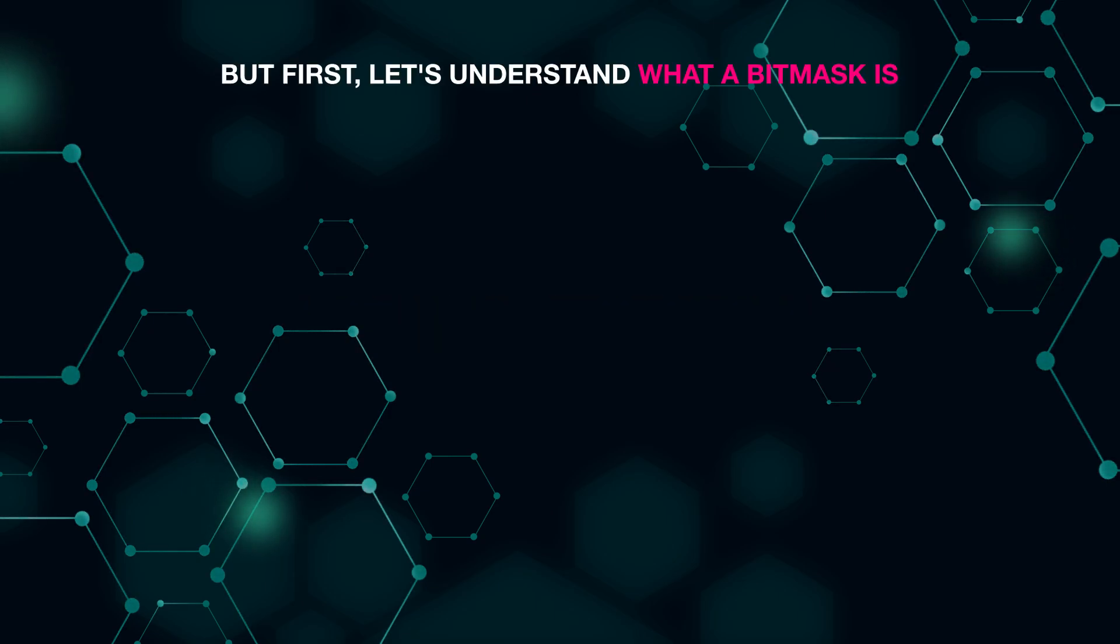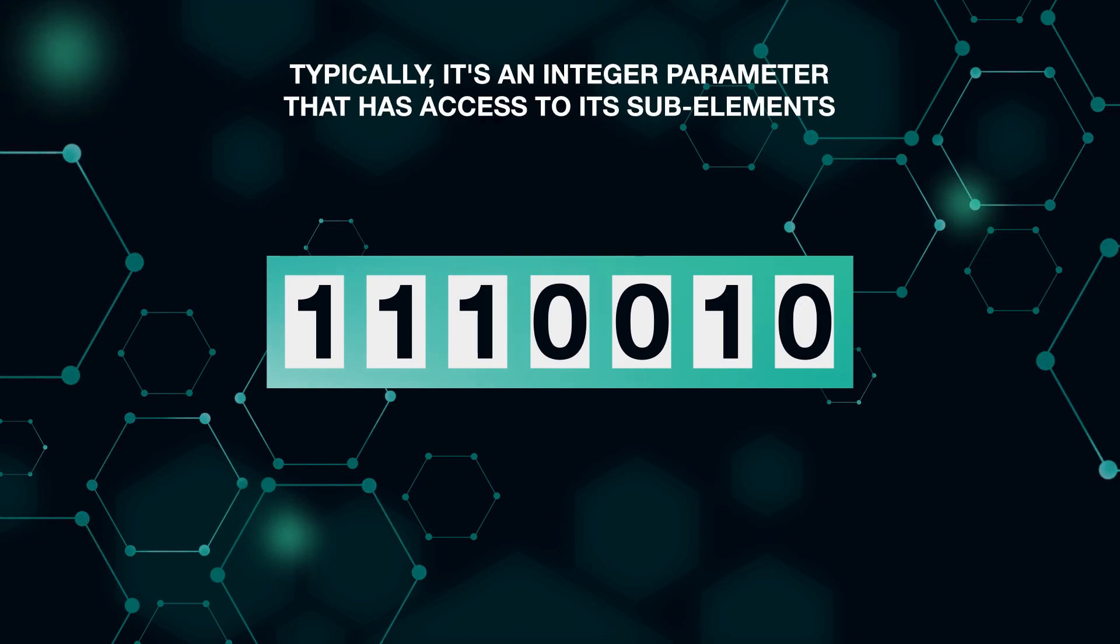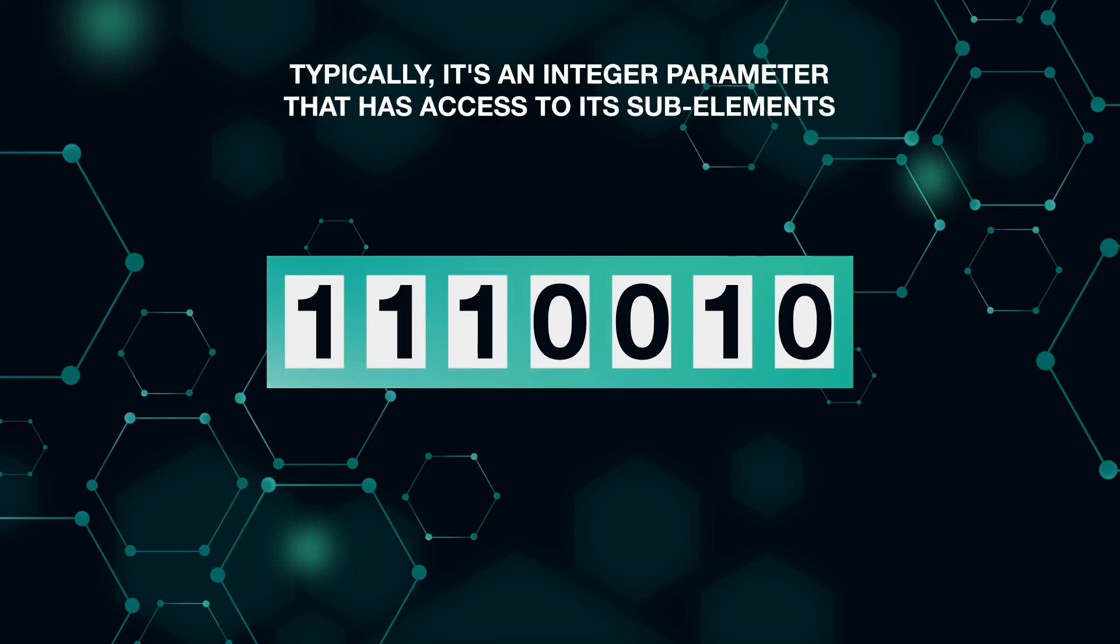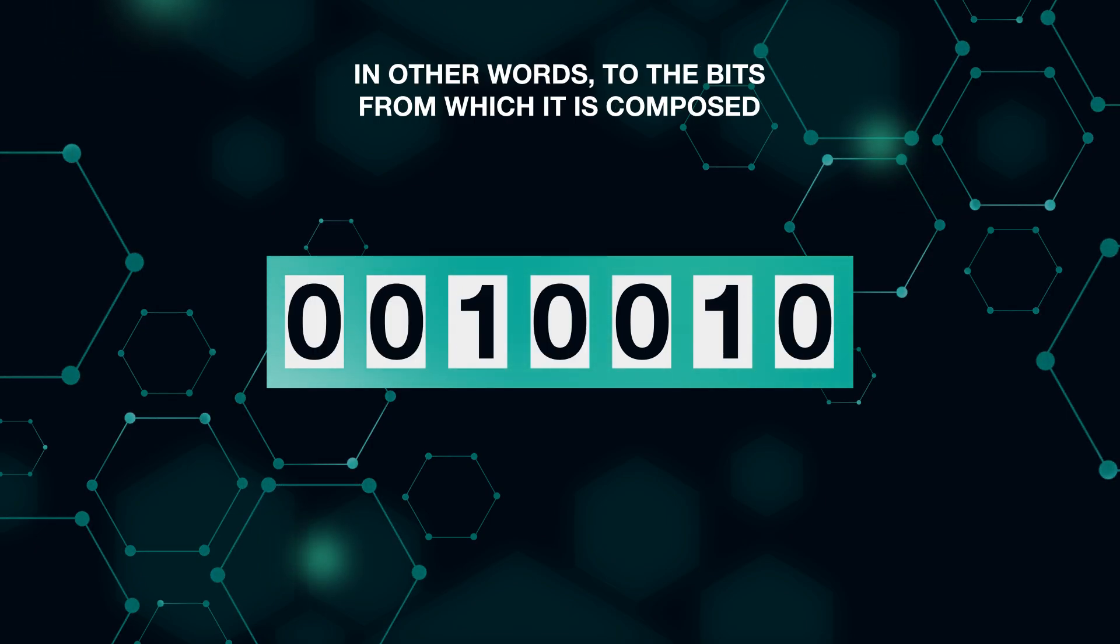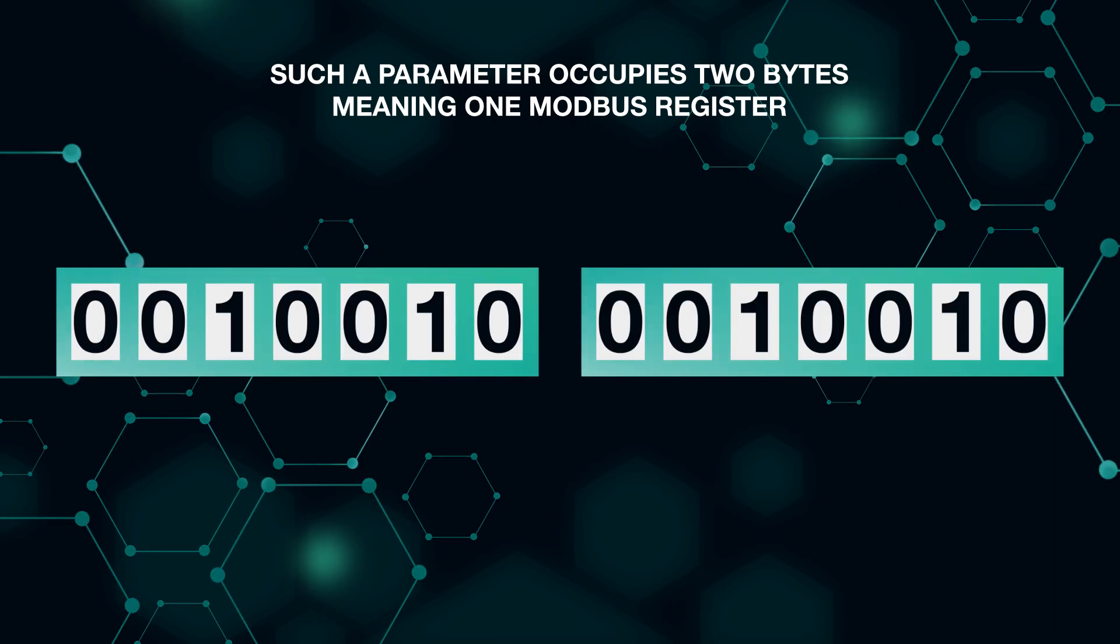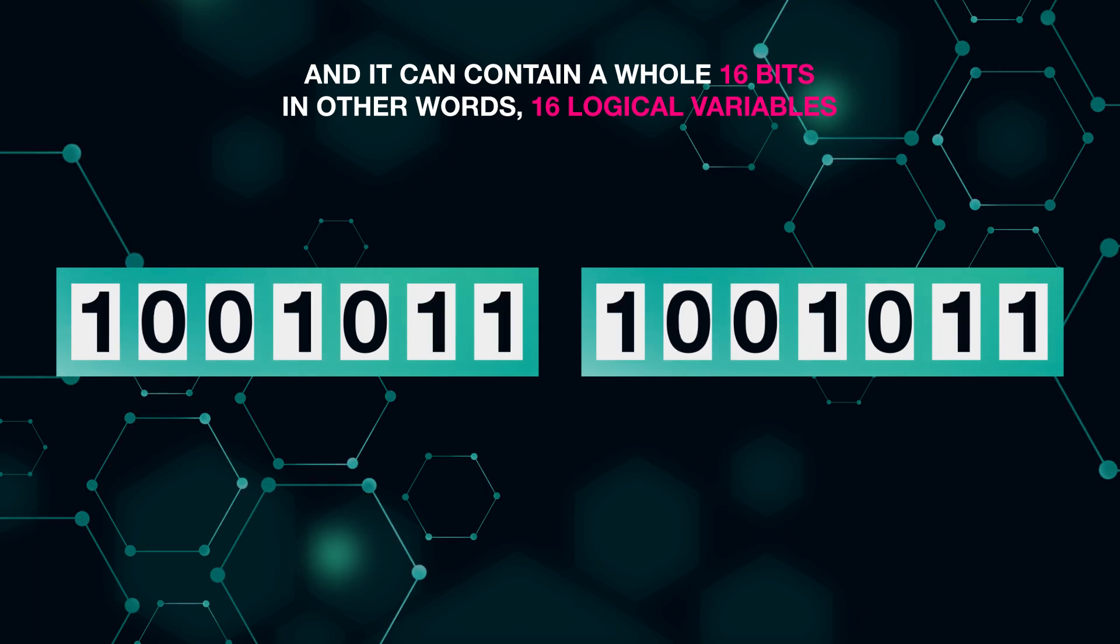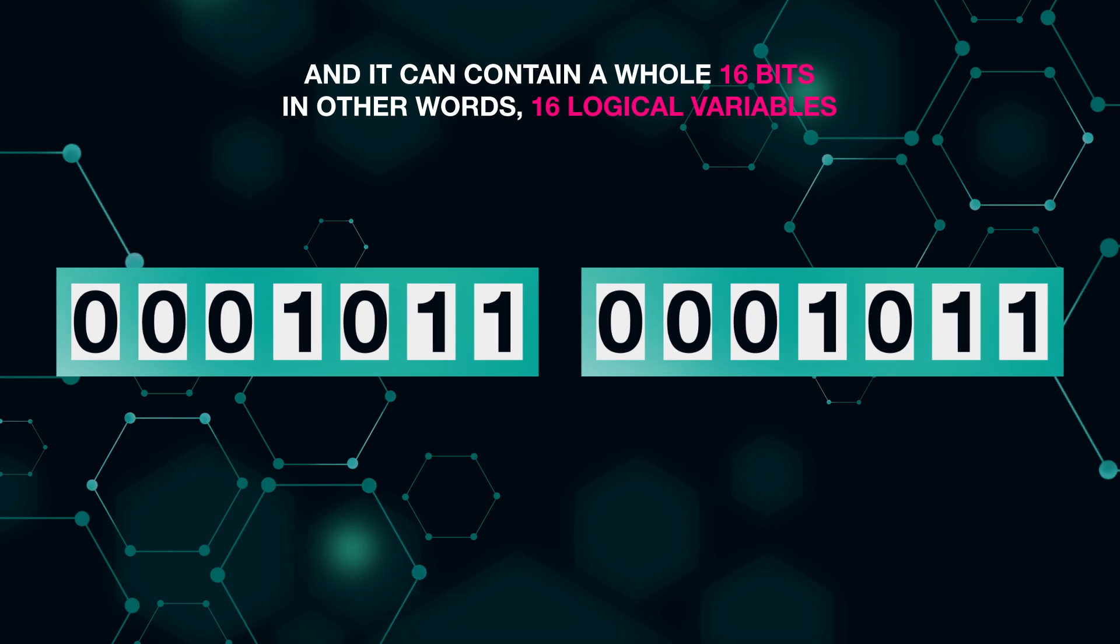But first, let's understand what a bit mask is. Typically, it's an integer parameter that has access to its sub-elements, in other words, to the bits from which it is composed. Such a parameter occupies two bytes, meaning one Modbus register, and it can contain a whole 16 bits—in other words, 16 logical variables.